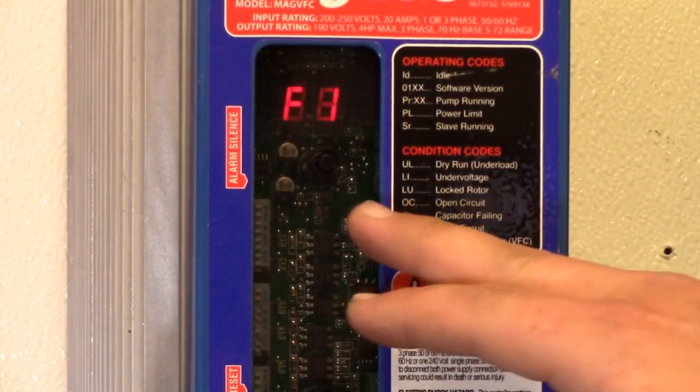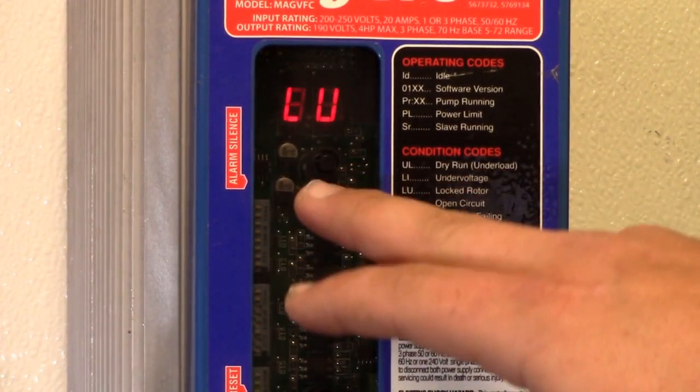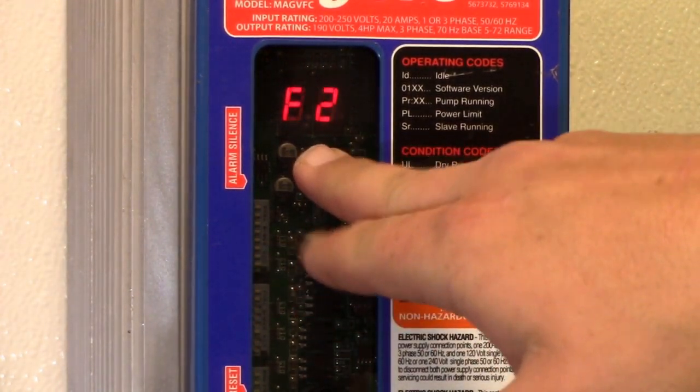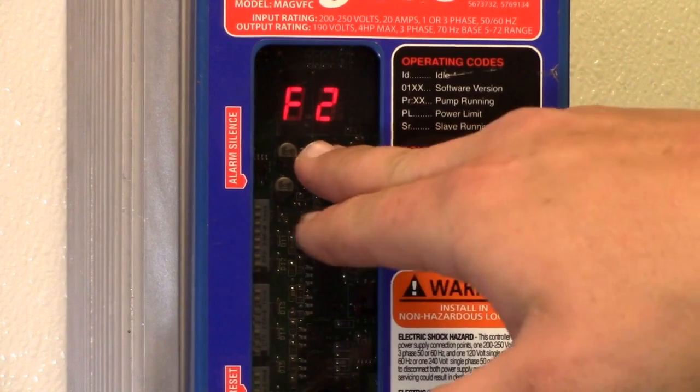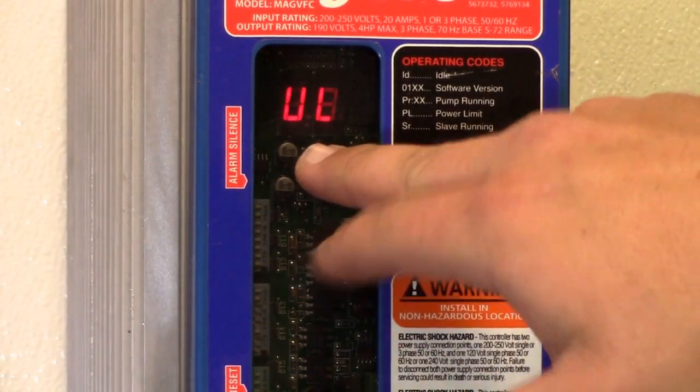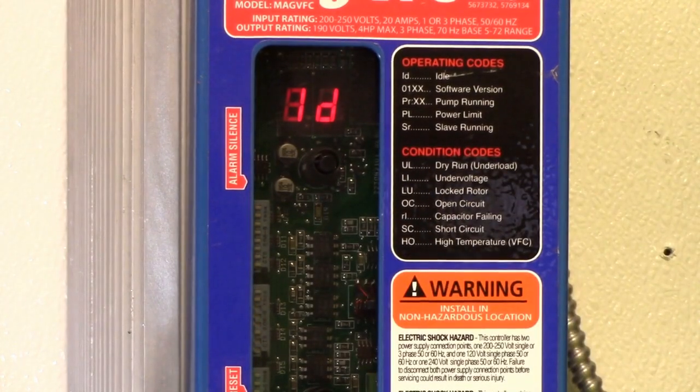Press it again to get to F1 for your second error: LU for lock rotor. And one more time for F2, your third error, which is UL for dry run. Press it one more time, right to Id, and then you're back in idle.